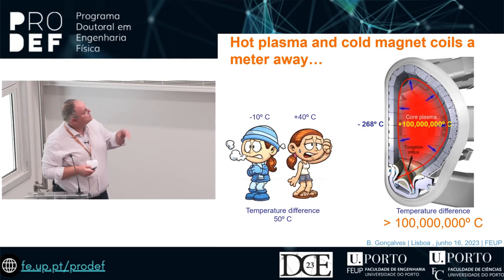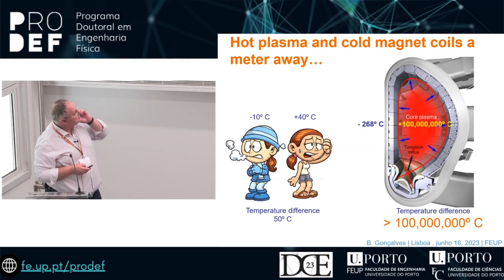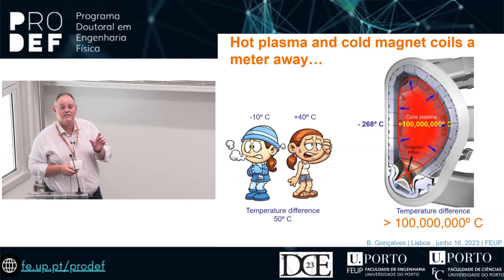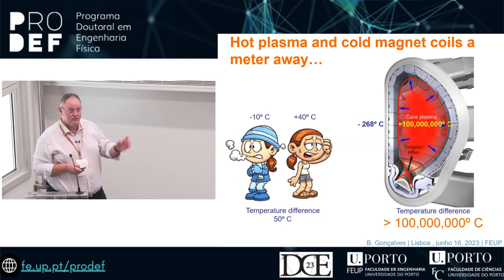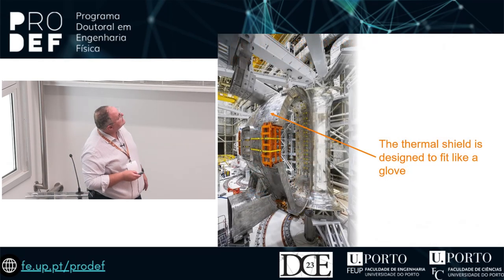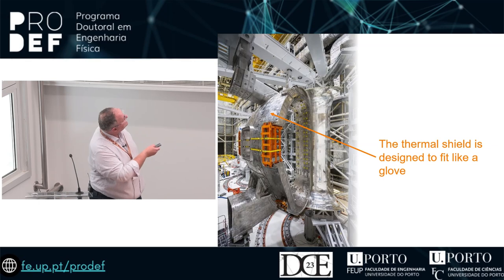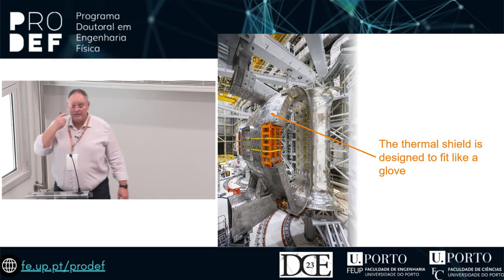Now, this is what I mentioned - we need the thermal shield. It's very hot; the temperature excursion from the inside to the outside is very large. So you need the thermal shield that needs to fit like a glove. Here you can see quite well the thermal shield, and you can probably even see some of the pipes around the cooling channels that had problems. So this is what is now being redone.